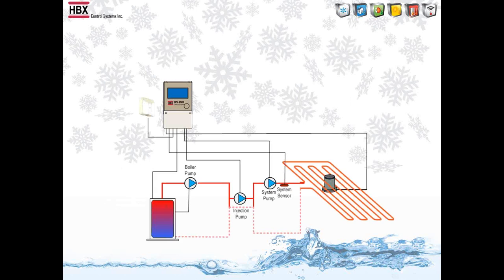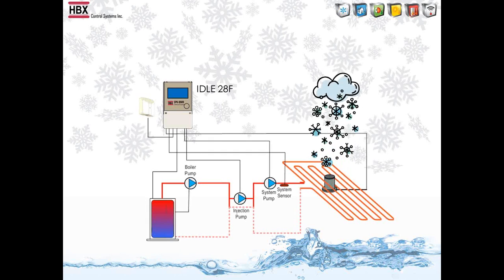To take it a step further, you will set up your control to an idle temperature. In this example we have 28 degrees. When it starts to snow, this is where you want your system to turn on and go into melt. So from here, we get out of idle and into melt. In this example, it's set for 50 degrees and we will melt the slab out of the snow zone.